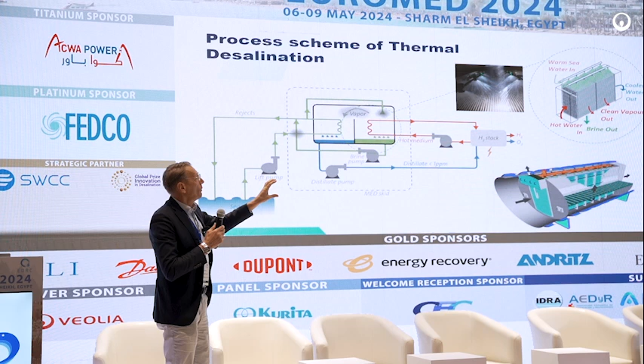I'll show you this: one containerized 40-foot solution with everything included, meaning storage of distillate water, seawater filter, startup heater, production, and EDI. Complete in this 40-foot container, it has a capacity between 70 to 120 cubic meters per day, sized to cover the capacity of one turbine, on wind turbines between 15 to 25 megawatts. This is what we offer at the moment for North Sea installations.